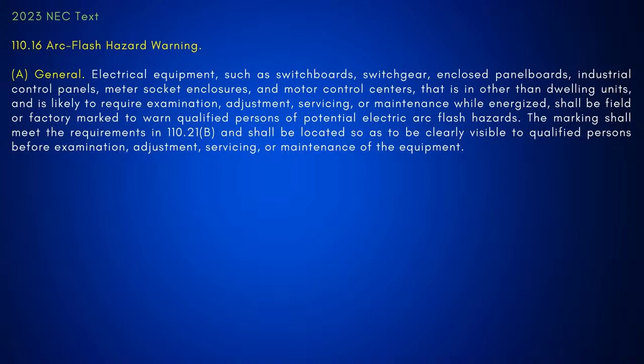Yeah, okay? I agree. So I just wanted to point out that even though an arc flash label is not required for your service equipment in a dwelling unit, it's still covered under 70E because it's a workplace. I'm not saying you have to put a label on there. You just have to realize that you still do not get a free pass on justified energized work. That's right. That's correct.